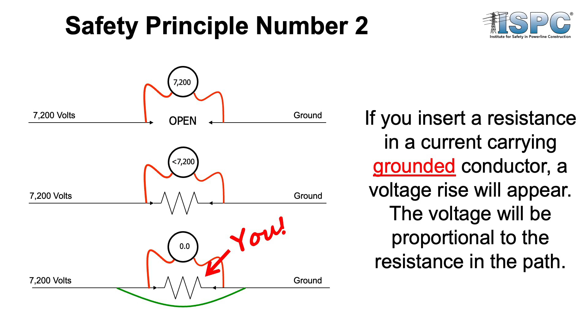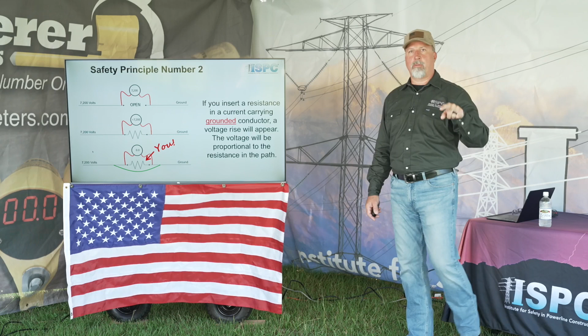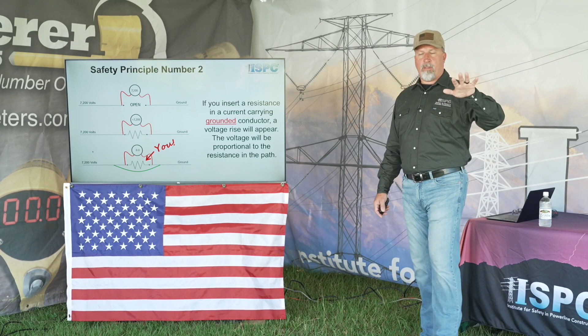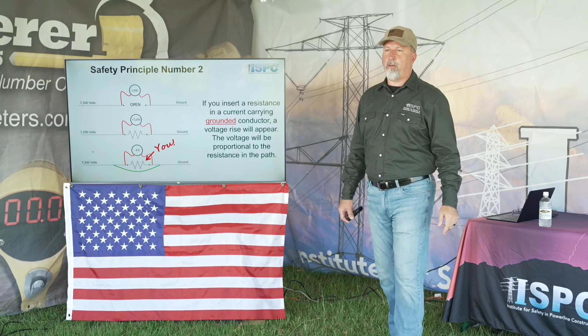That resistance in there could be you, okay? There's going to be a voltage rise across that resistance. And then obviously the last one there depicts you as the resistance, and if you bond or ground across that open point or resistance, that voltage goes to 0, right? Because that jumper or that bond across that resistance or open point is less resistance than you are. So more current's going to follow that path, okay?